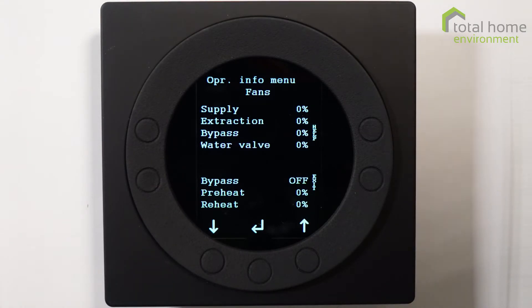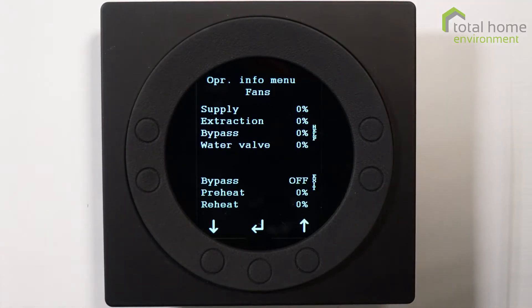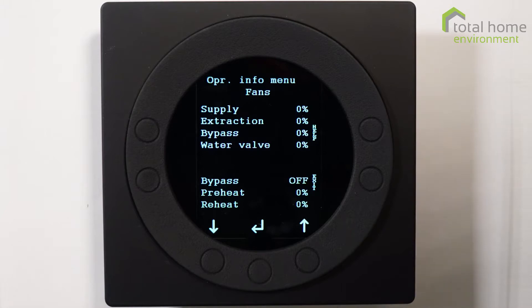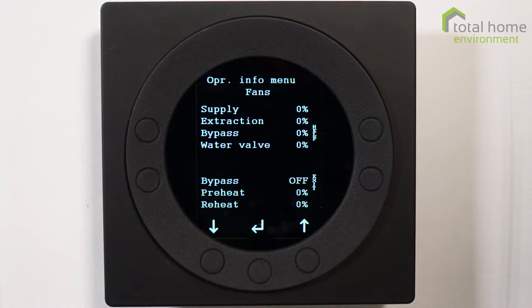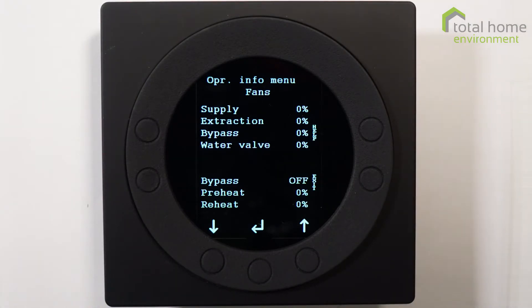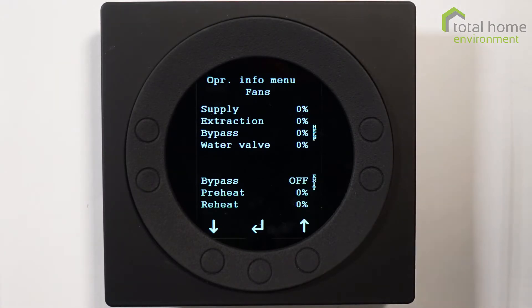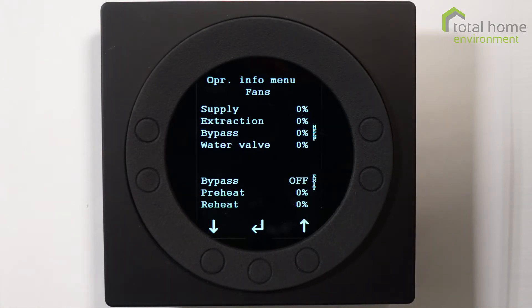Currently on this machine the bypass is off. Preheat is zero percent and reheat is zero percent. Most people won't have preheaters in the UK - we don't get cold enough for preheaters. Some will have a reheater unless you're a passive house, and then the chances are you won't have it, although just to be awkward, some passive houses do have a preheater.